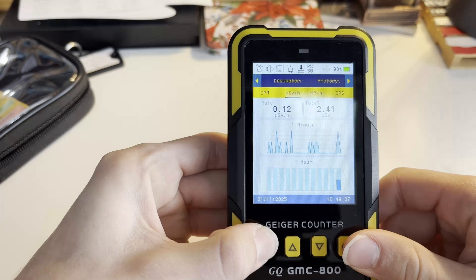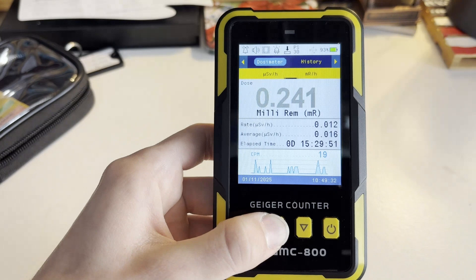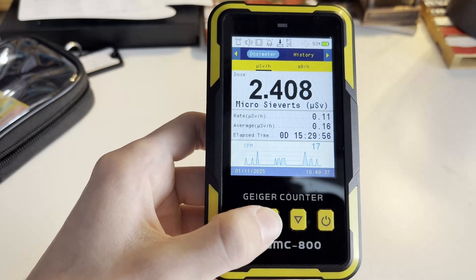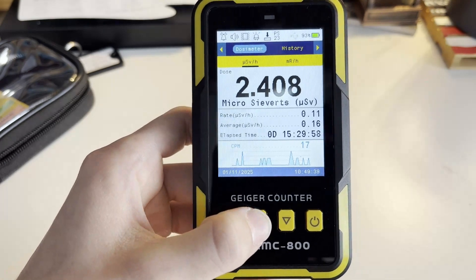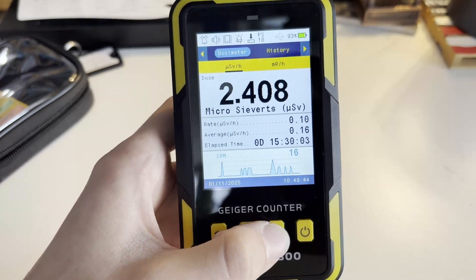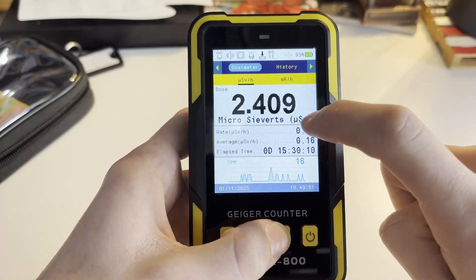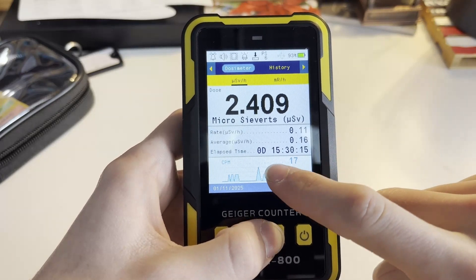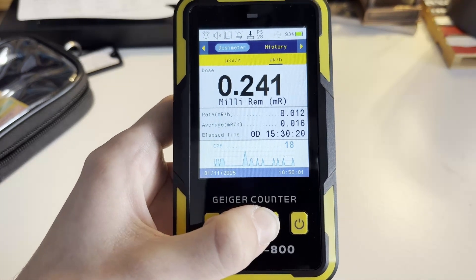The next function is the dosimeter function, which like the graphic screen compounds the exposure you've received. It's shown in either micro sieverts per hour or millirem per hour. I would not trust this entirely for dose rates, as this is not energy compensated like the RadiaCode. The first screen shows the reading in millirem, the current rate, the average rate, and how long it's been since the device was first turned on.